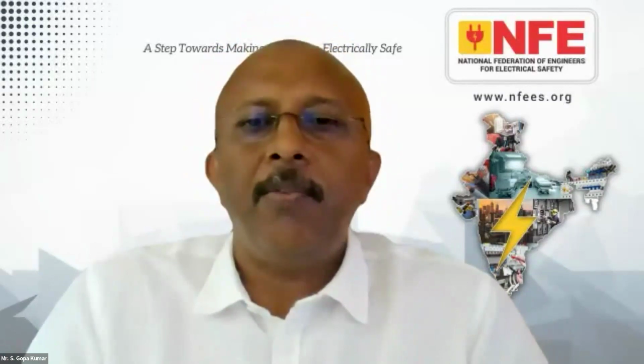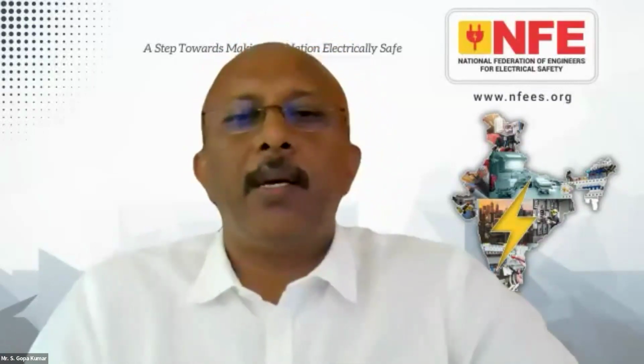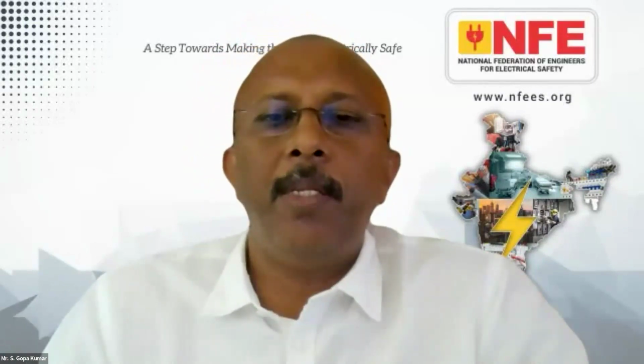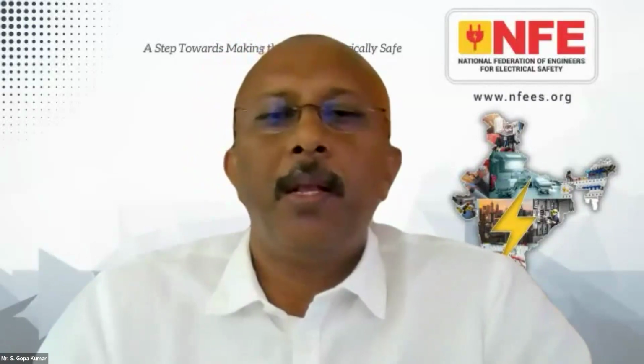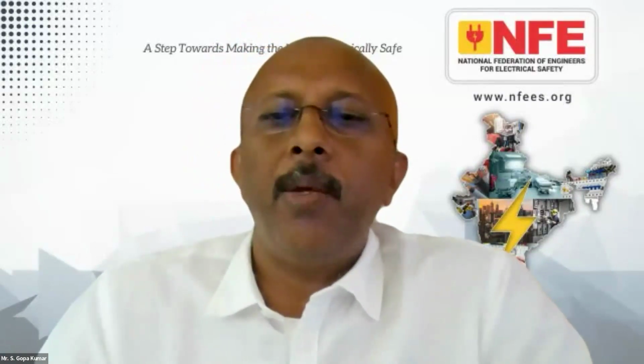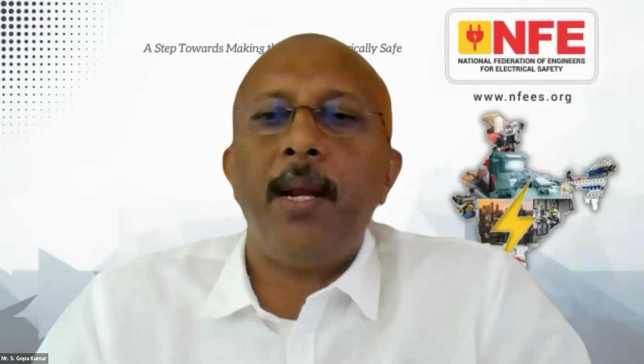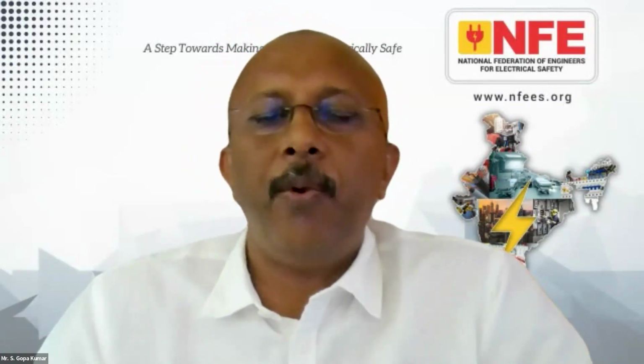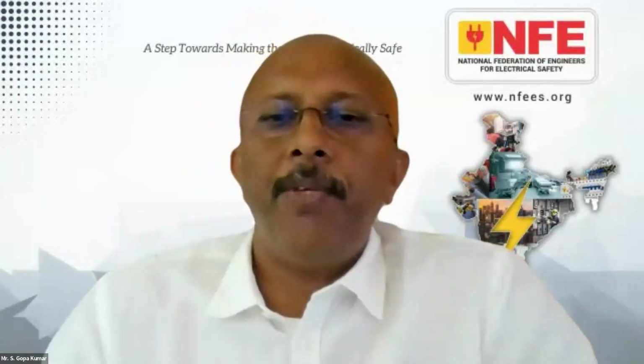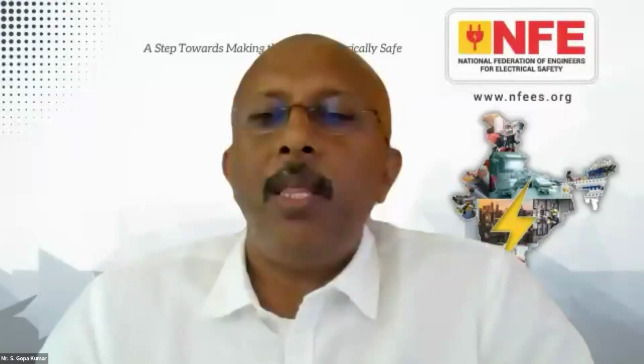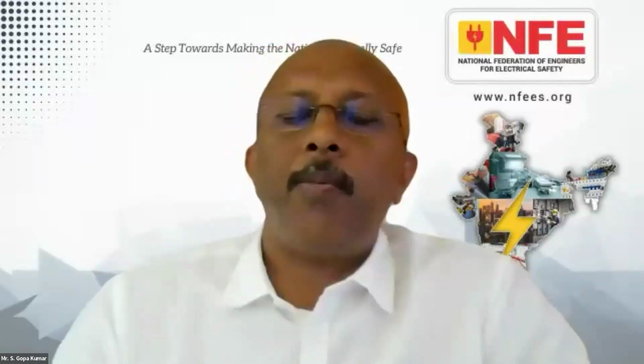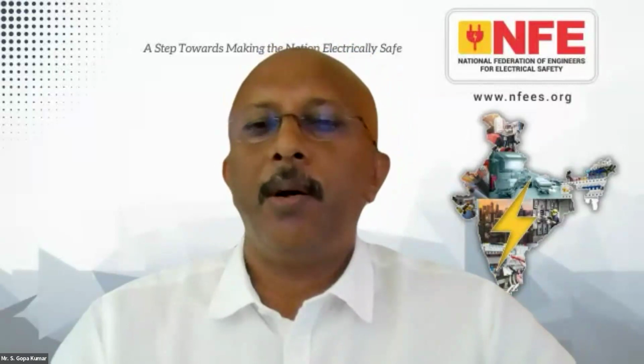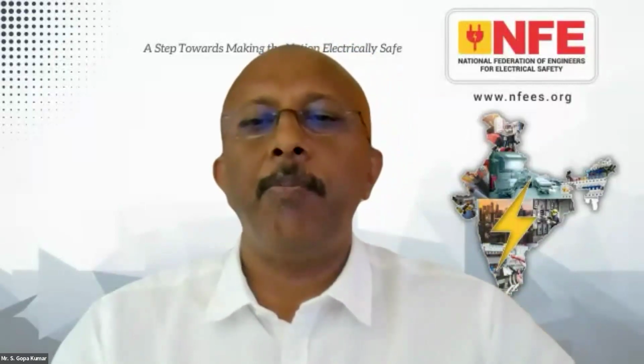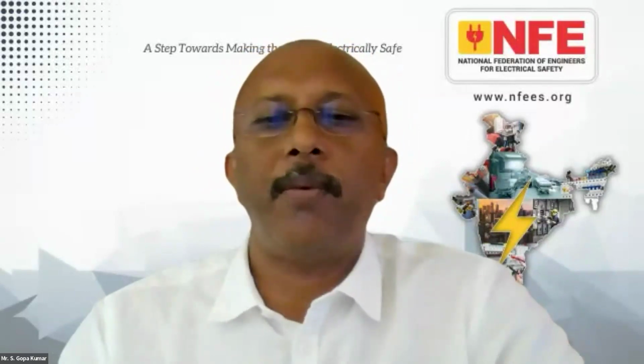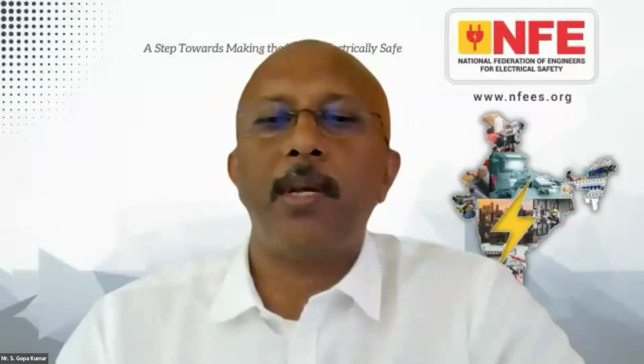We are supposed to use a TNS system for medical locations — group 0 and group 1 locations in the hospital. It means it's a 5-wire system: three-phase, one neutral, and one separate protective earthing conductor coming from the neutral at the substation. All class 1 metallic body parts or protective terminals of class 1 equipment, and technically the exposed and extraneous conductive parts, must be bonded to this 5th wire, called the protective earth conductor. That is the correct way. Thanks for the question.